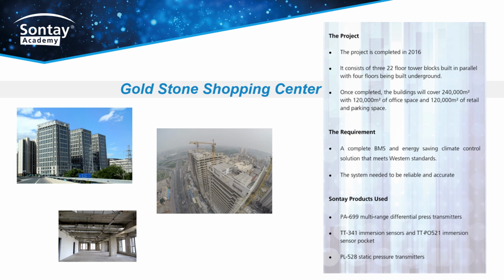Within this, they used Sontay products such as the PA699 multi-range differential pressure transmitters, the TT341 immersion sensors and TTPO521 immersion sensor pockets, along with PL528 static pressure transmitters. Accurate sensor data is key to optimising any facility, and none more so than shopping centres. Maintaining correct pressure regimes between the mall and shopping units is an important consideration when developing energy-efficient strategies. Similarly, ensuring only the required amount of heating and cooling water is distributed around the centre means that pump energy can be reduced to supply only the required flow to the centre.